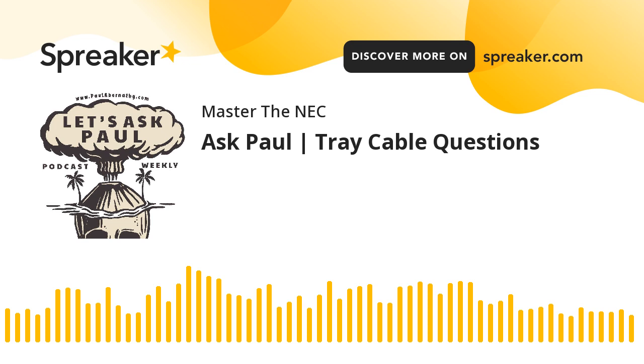Now, tray cable in the NEC, the National Electrical Code, is covered under Article 336. It is a non-metallic product, very similar to a non-metallic sheath cable, but its construction can be different. Its construction and the thickness of the sheathing are pretty much governed by UL standard 1277, okay? That's a little different because non-metallic is covered under 719, but this is 1277. So it has its own construction requirements.